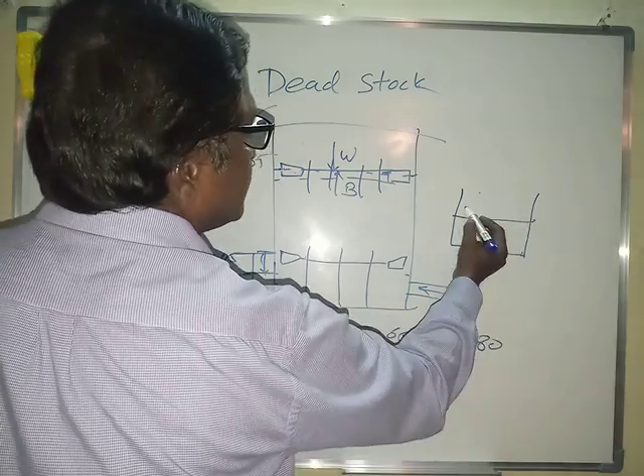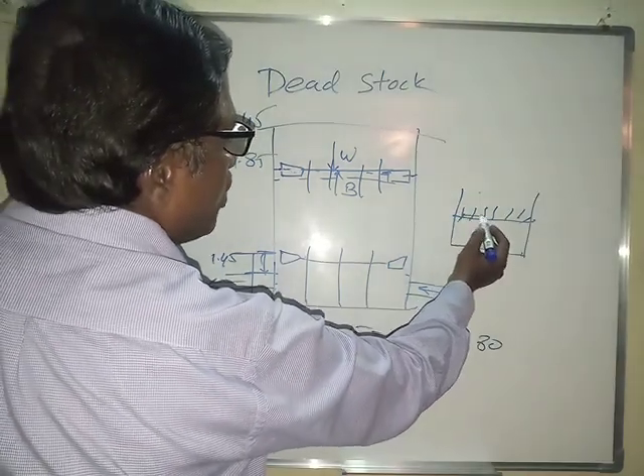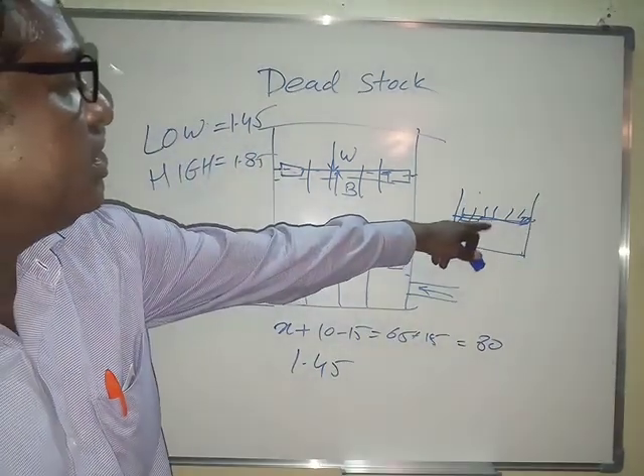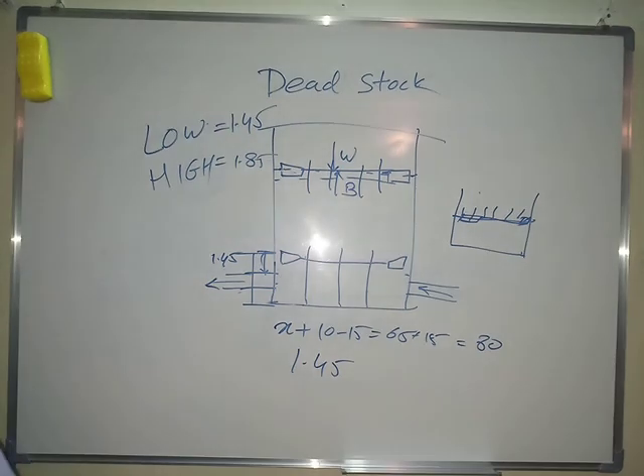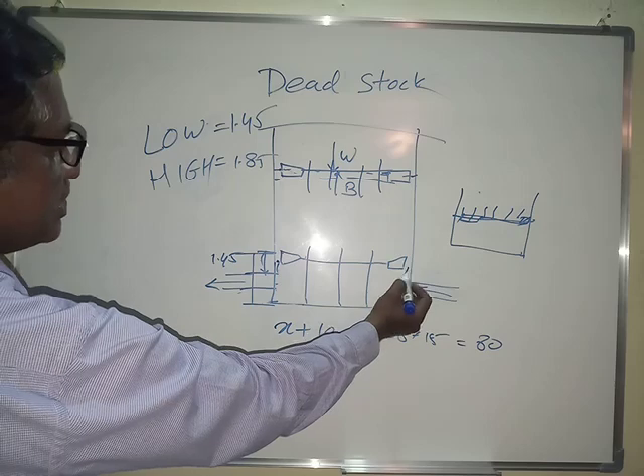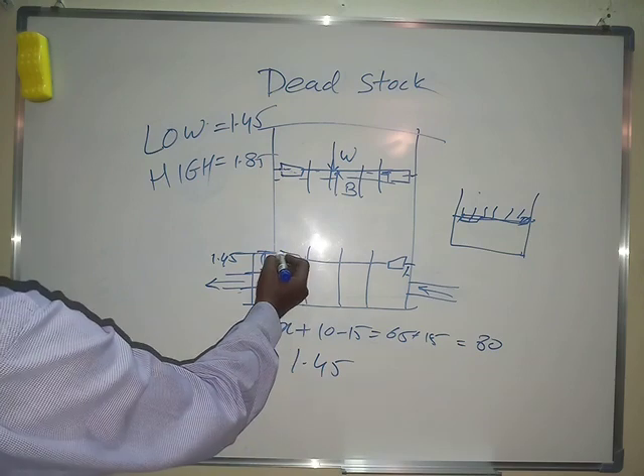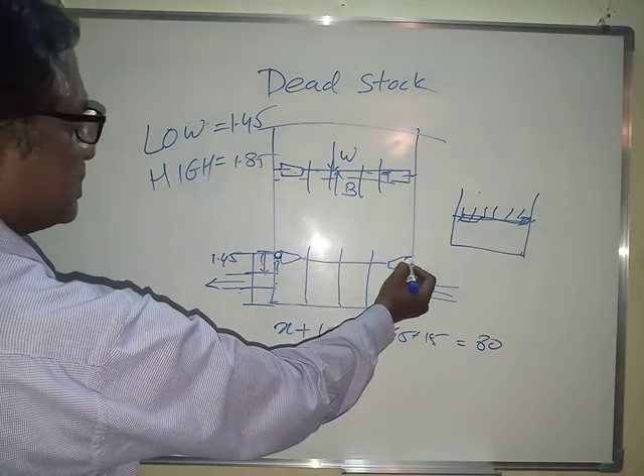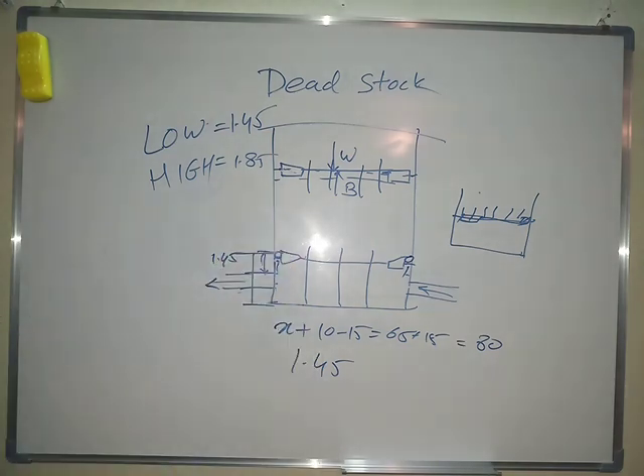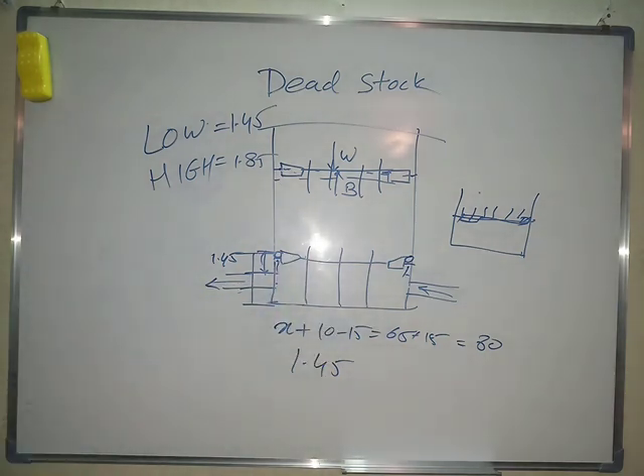If this is the exposed surface area, from every place it will get evaporated. But if your roof is touching on top of it, then there won't be any atmospheric air available and it will not allow evaporation. So the only possibility of evaporation is this place and this place, which is 200mm this side and 200mm this side. But here again we are sealing by using the ring seal, so we are restricting the evaporation loss from here. So that is the advantage of the floating roof tank.